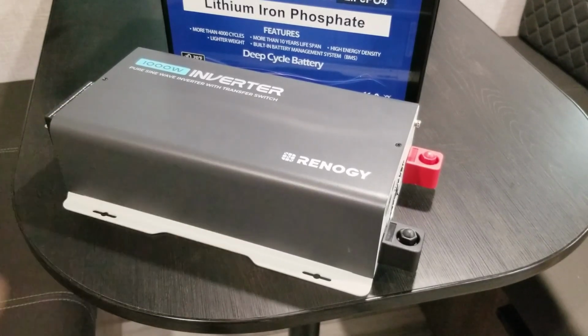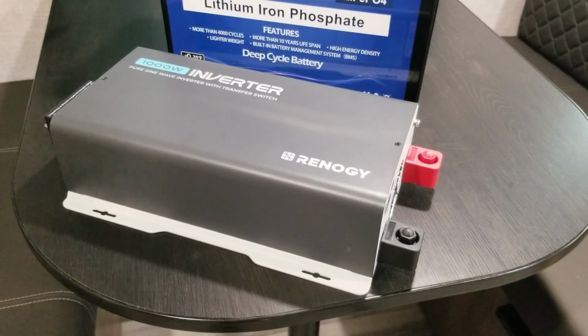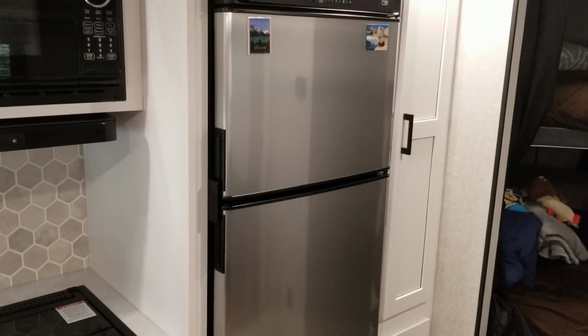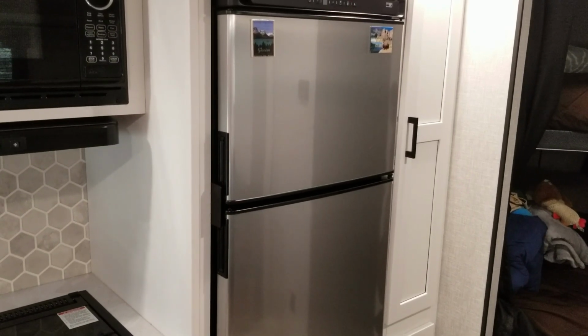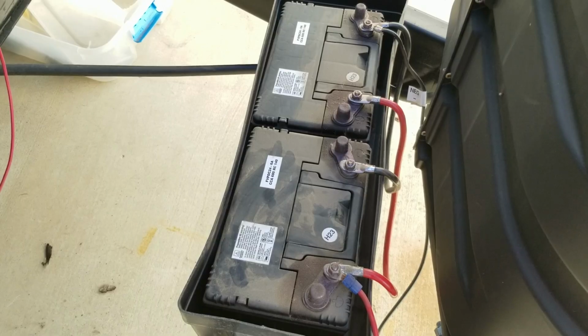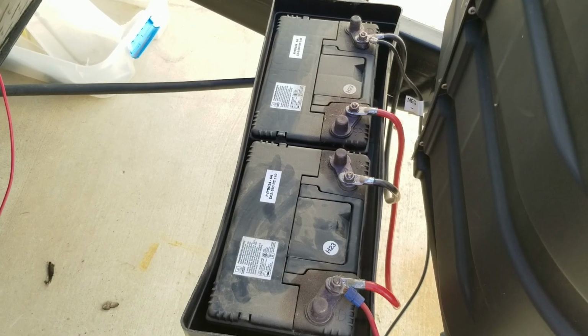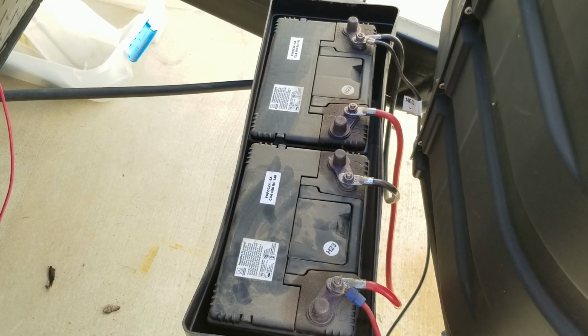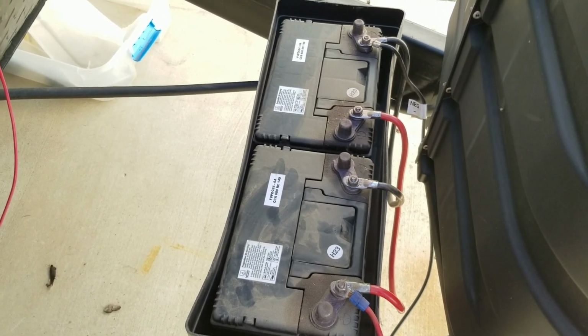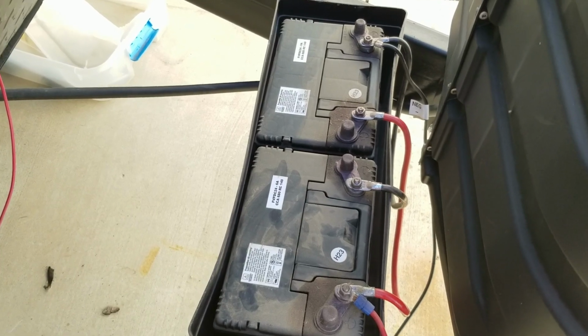Things like your power inverter here are going to shut off when they get below, say, 11 volts or so. If you have a DC fridge, it will probably also shut off when the voltage gets too low. That means the usable amp hour rating for these batteries is much less, say 40-45 amp hours per battery, for a total of 80 to 90.